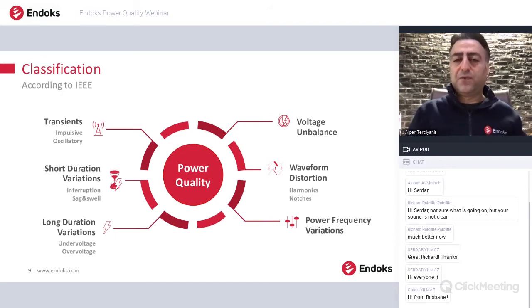On the medium voltage side, of course, imbalance can create some triplen harmonics, and these triplen harmonics can cause resonance issues on the medium voltage network. For waveform distortion, harmonics are the common parameters, and notches are another one. Notches are mostly caused by power electronics devices like motor drives, or by switching some loads. Harmonics can be generated by power supplies, converters, inverters, motor drives, even some lighting.